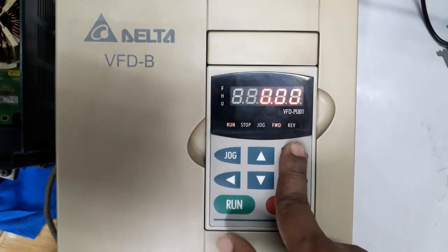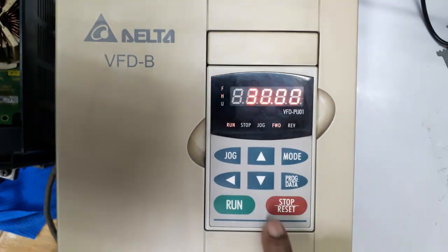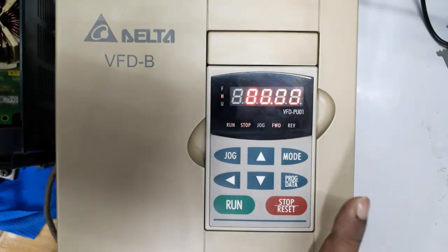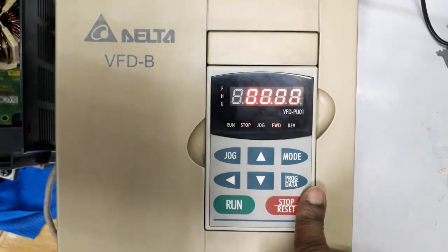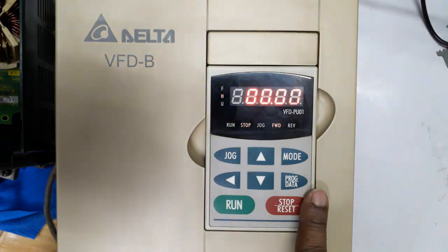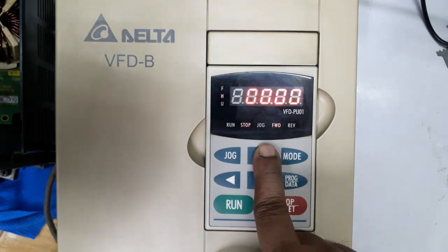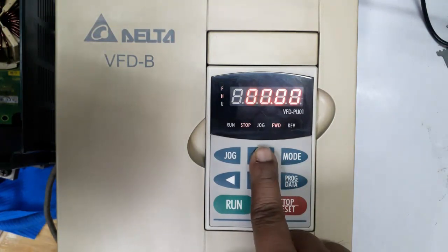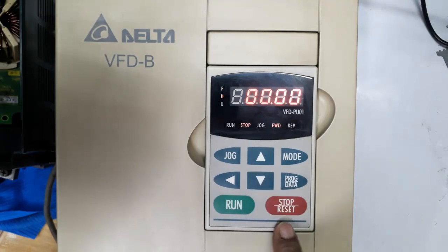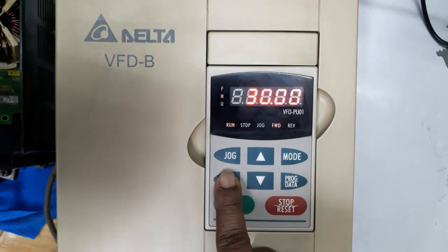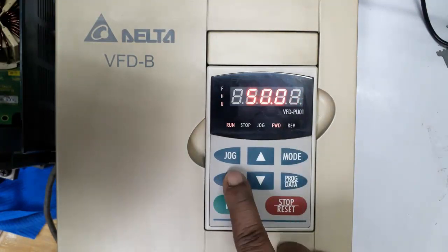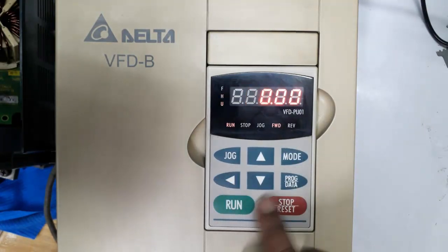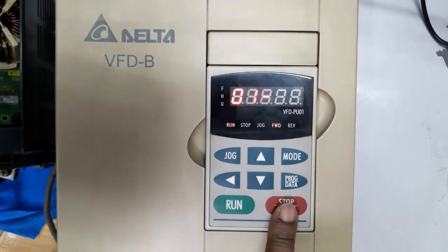Now the inverter will run from lower limit to higher limit in 5 seconds and stop, taking 10 seconds, because we changed deceleration time from 1 to 10 seconds. Actually, acceleration and deceleration time are related to lower limit to higher limit frequency up and down. It's maintaining to control the induction motor speed.